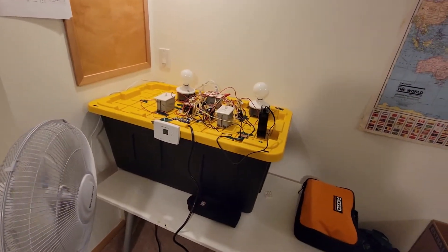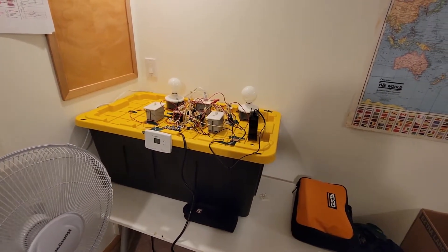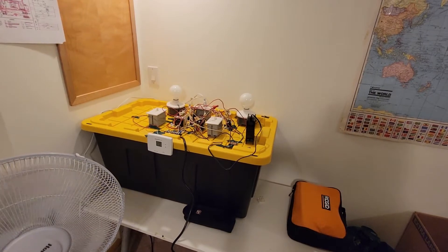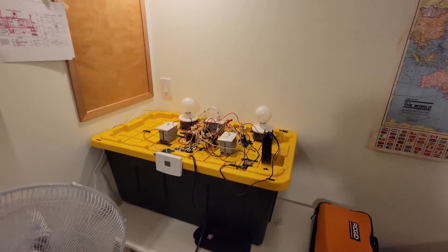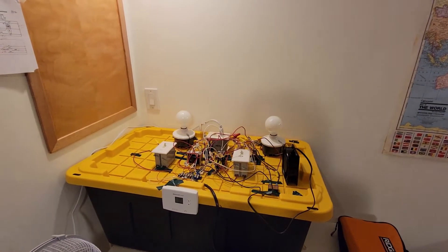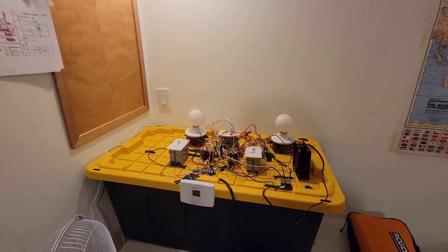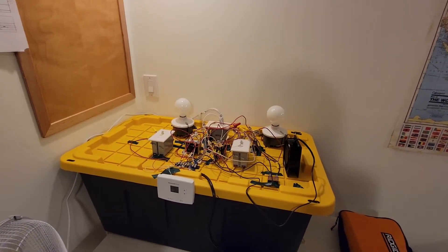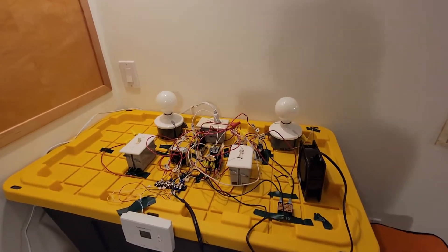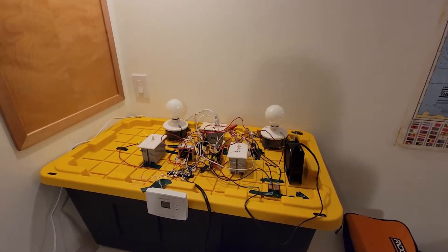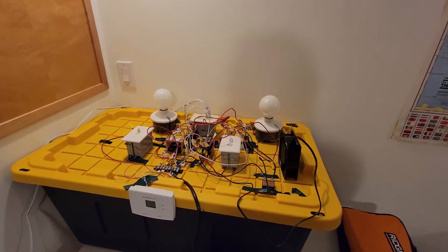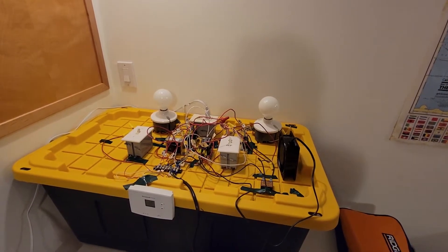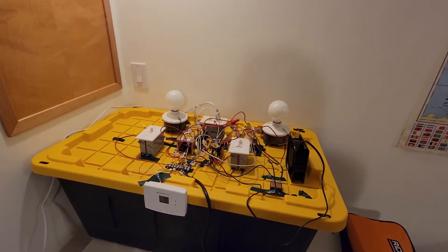The next step is to check the heating mode. When I turn on the heating mode, it's going to turn on this light bulb right here, which represents my furnace. That's going to send a heating element, light up and heat up my sequencer. So while the gas furnace is burning and getting the heat exchanger working, the sequencer will be controlling the fan.